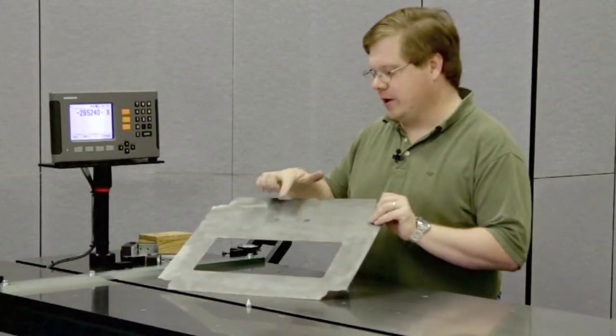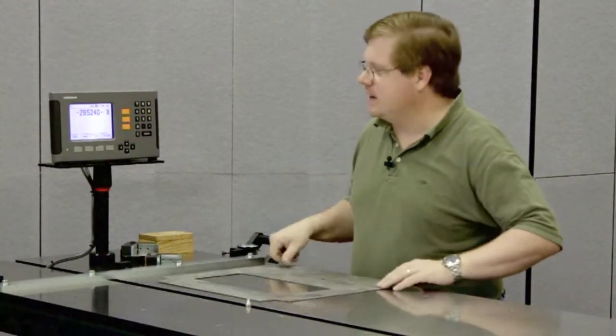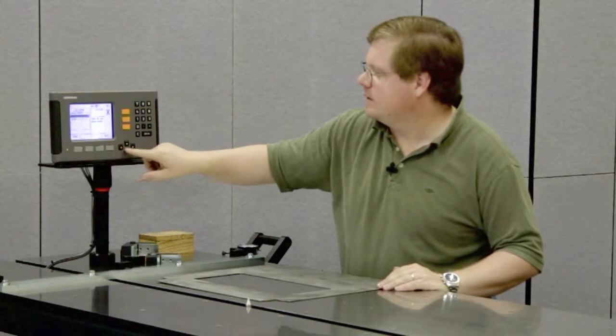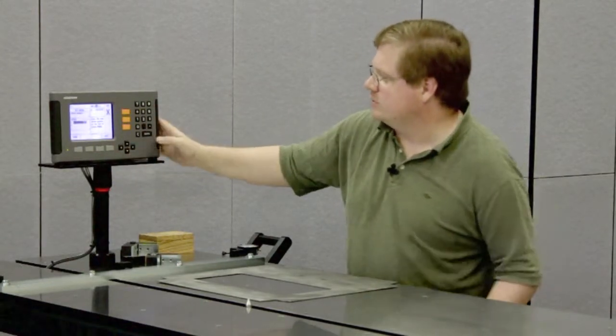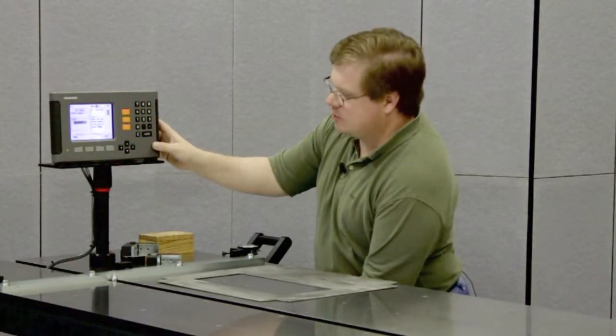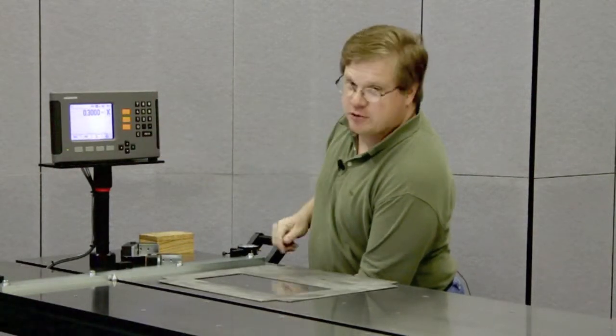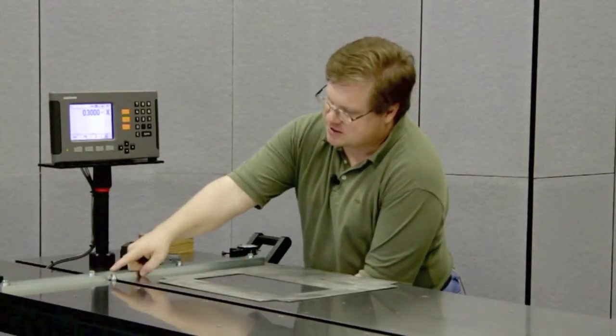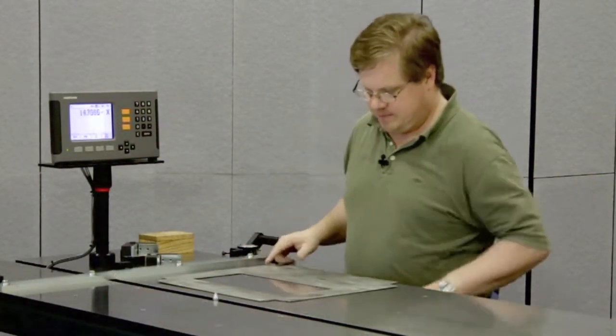If you want to check hole locations, you can do this by setting up a datum, and we'll set the X equal to half the diameter of the probe tip. You do that right up against the stop bar. So now it's measuring to the center of that point.